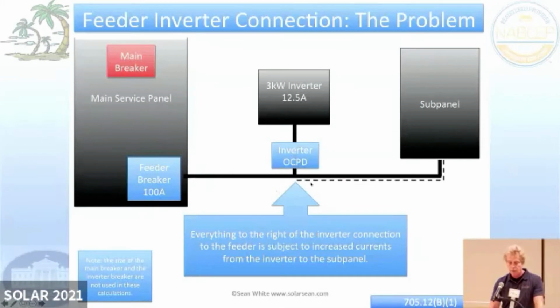But going this way, if the sub panel was overloaded and power strips are going into power strips, we could potentially have 112.5 amps going on this conductor. And this is just for an example. Maybe it would be a 100 amp inverter, but just for this example, we're doing 12.5.